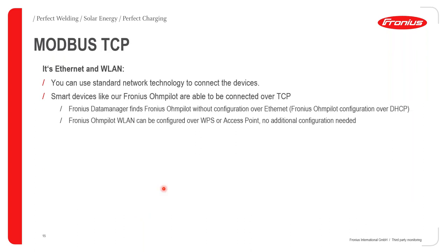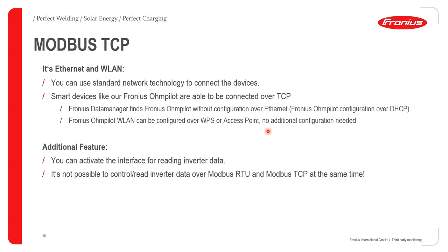For Modbus TCP, this is Ethernet-based. You can use standard network technology to connect devices by simply plugging them in. Smart devices like the Fronius Ohm Pilot are able to connect over TCP, and the Fronius Data Manager automatically finds connected devices without any additional configuration.